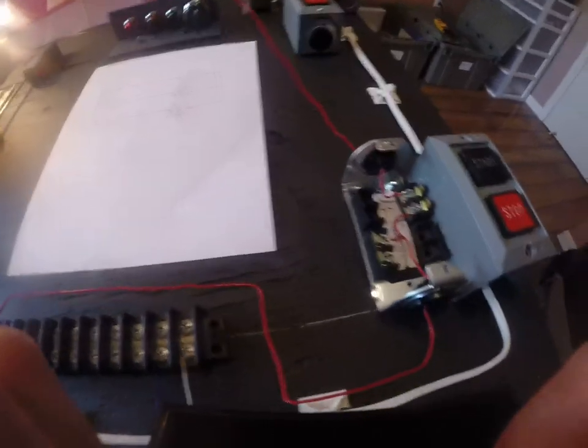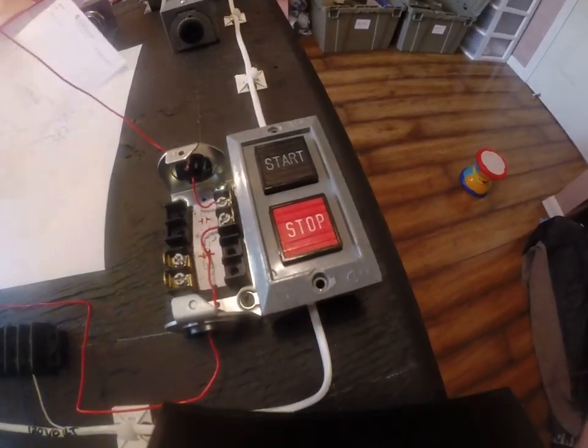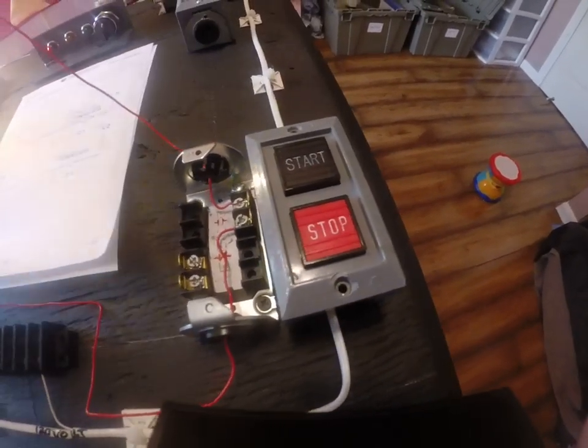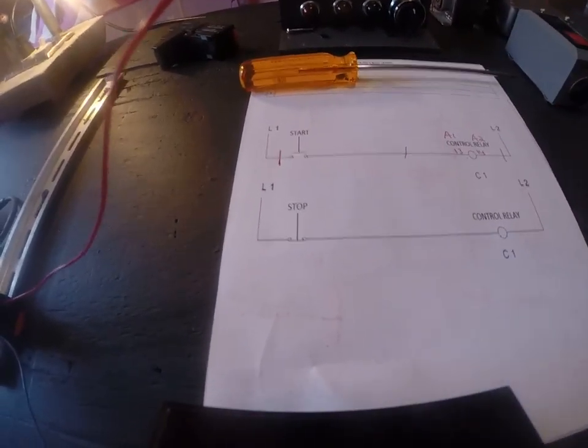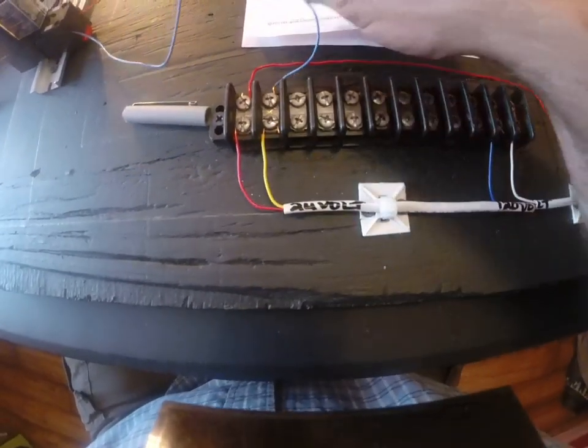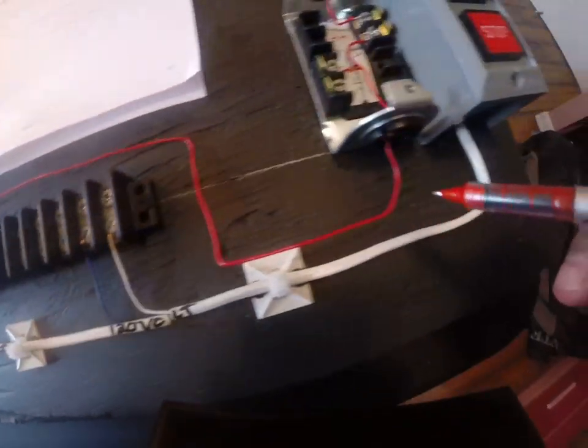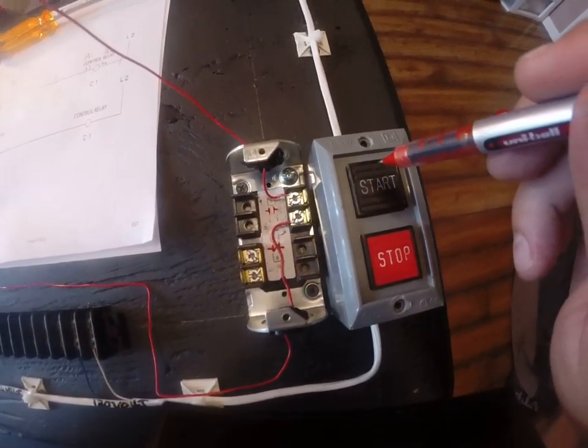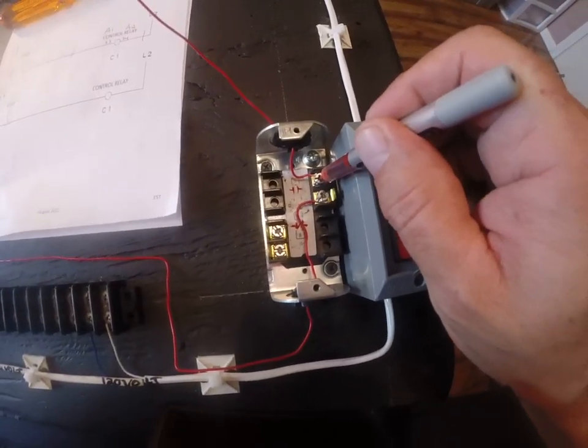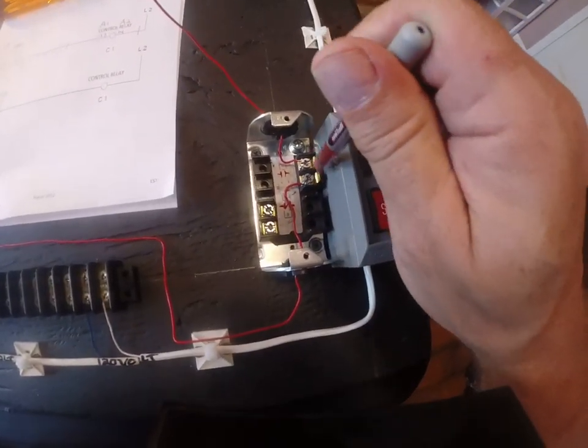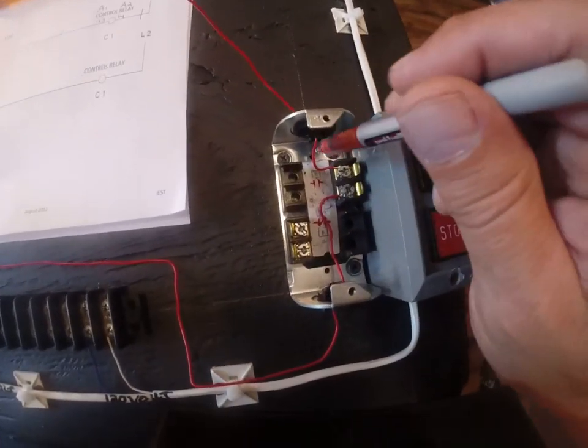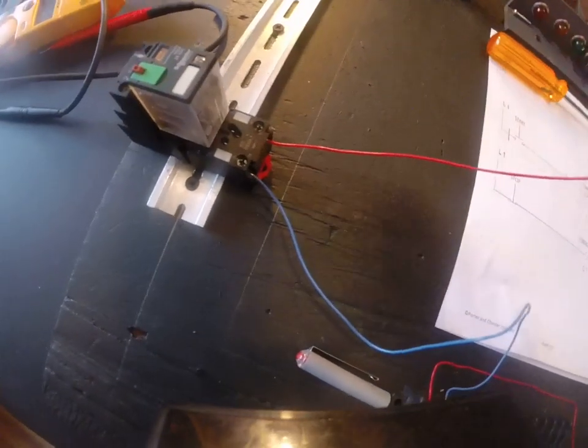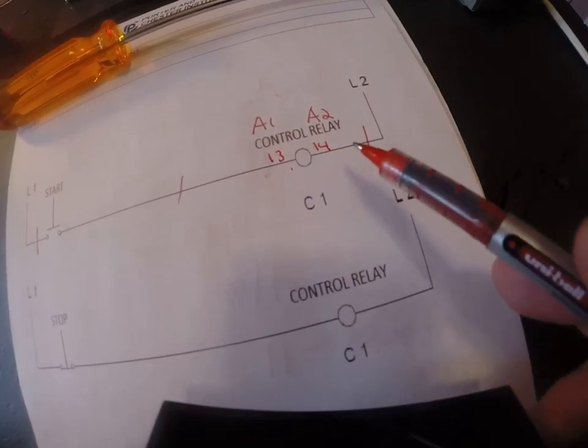The first wire on that drawing goes to the first screw of the start button. And that was this drawing here. And if we take a look at this drawing, right now we have the first wire from the source going to the first screw. Wire from my 24 volt source. It's red. It leaves the source. Comes into the first screw of the start button. There's a second screw of the start button that doesn't do anything until I press it. But when I do press this button I close these contacts I make this circuit jump to here through the button. Then those electrons leave this red wire and come over to 13 on this base. That's this from this screw to 13.